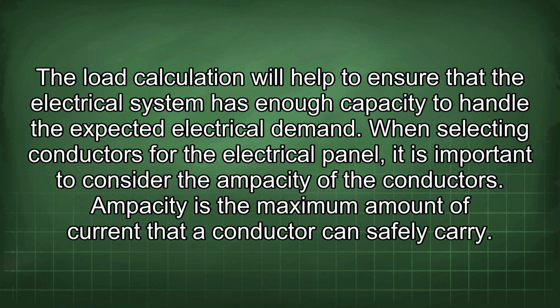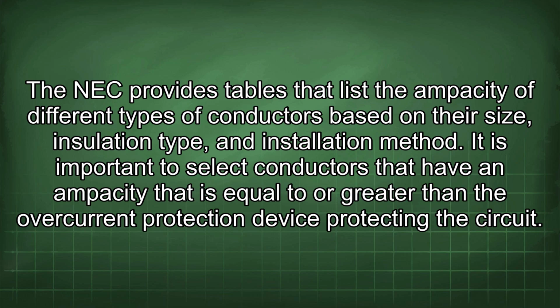When selecting conductors for the electrical panel, it is important to consider the ampacity of the conductors. Ampacity is the maximum amount of current that a conductor can safely carry. The NEC provides tables that list the ampacity of different types of conductors based on their size, insulation type, and installation method. It is important to select conductors that have an ampacity that is equal to or greater than the rating of the overcurrent protection device protecting the circuit.